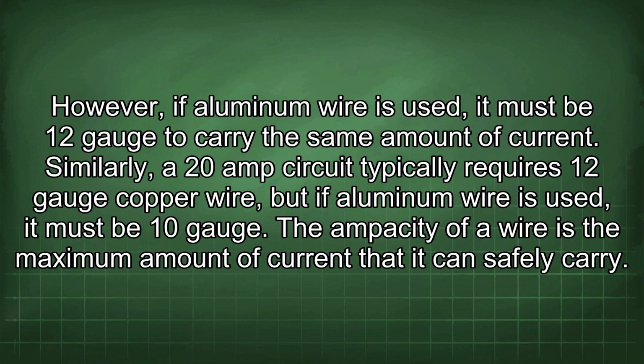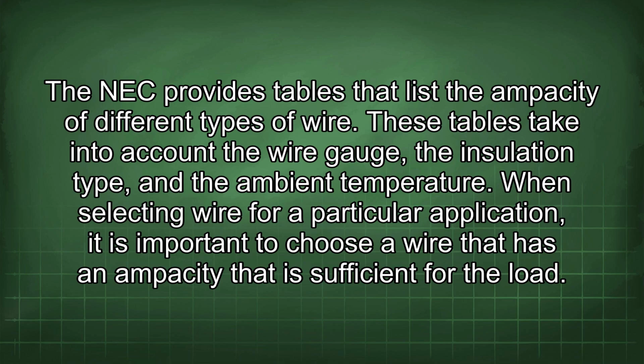Similarly, a 20 amp circuit typically requires 12 gauge copper wire, but if aluminum wire is used, it must be 10 gauge. The ampacity of a wire is the maximum amount of current that it can safely carry. The NEC provides tables that list the ampacity of different types of wire. These tables take into account the wire gauge, the insulation type, and the ambient temperature.